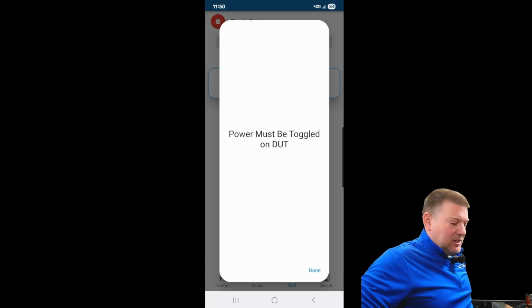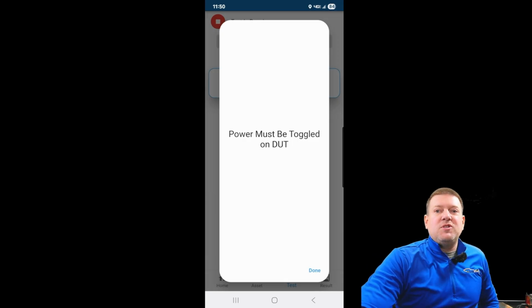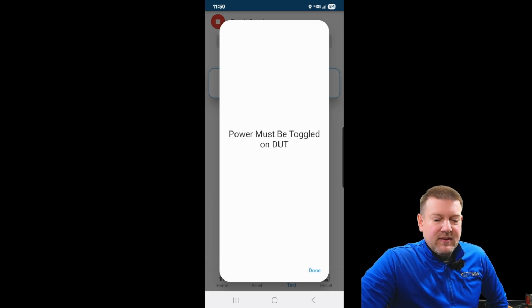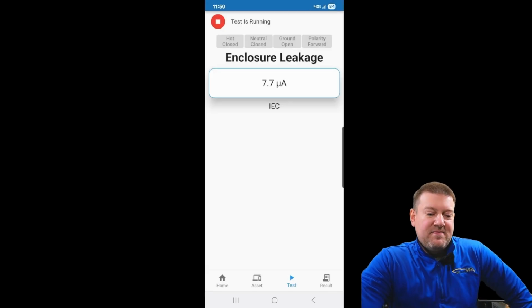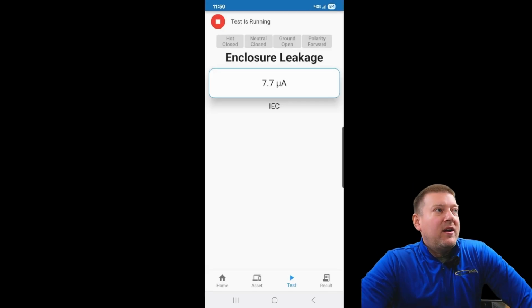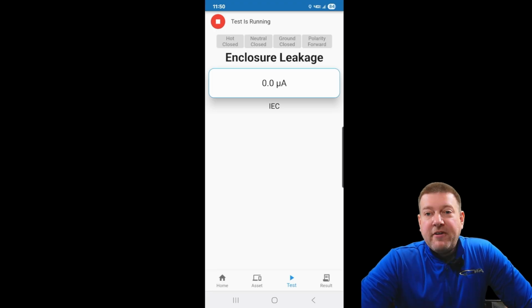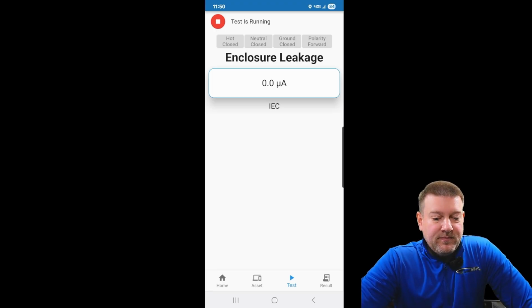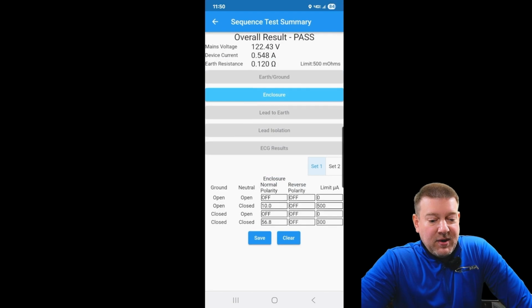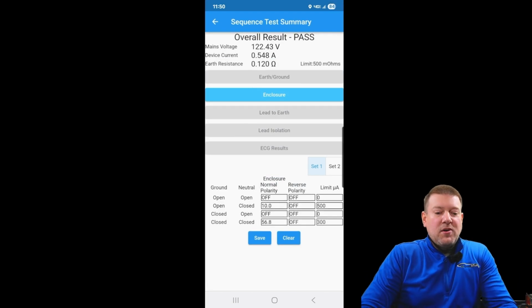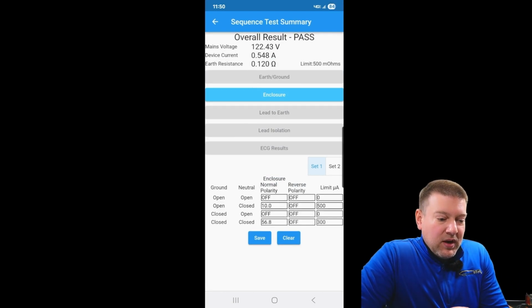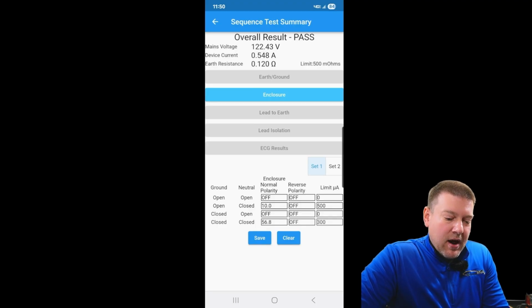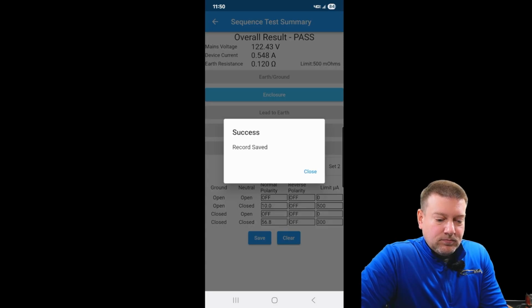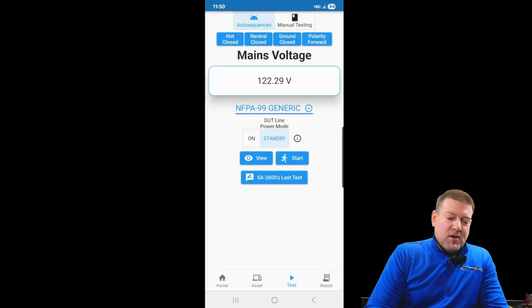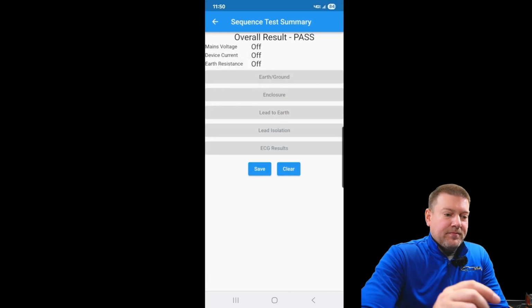Now it's saying the device power needs to be toggled. So we shut it off. And I click done. And now it's going to go ahead and it's going to run the rest of the electrical safety checks with the device now powered off. And there we go. Okay. So I have a result saved here, and we can go through and we can see all the different results that I had. However, I'm just going to go ahead and click on save. And now those results are saved here on the device.